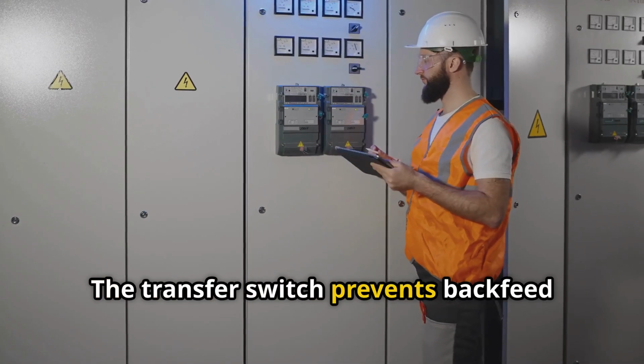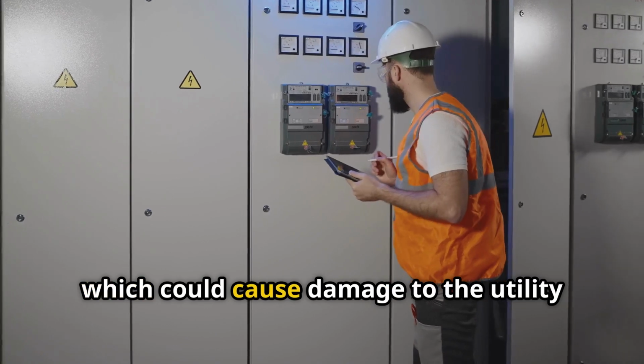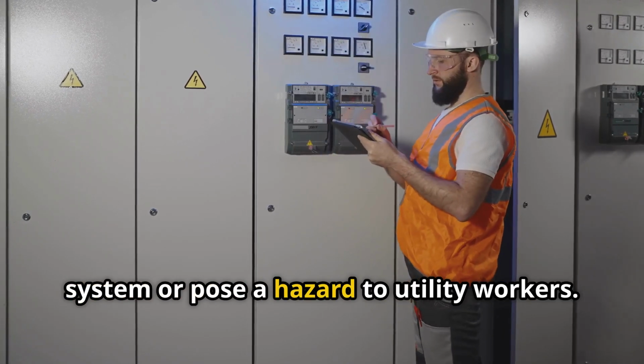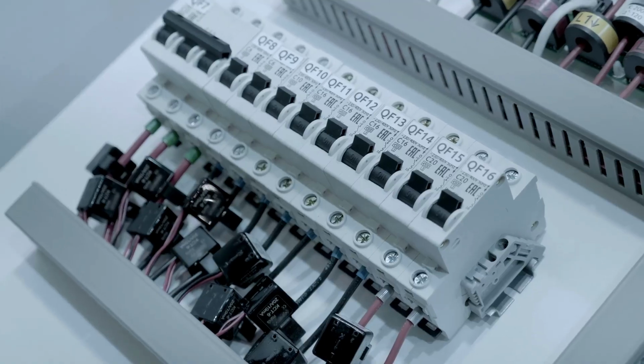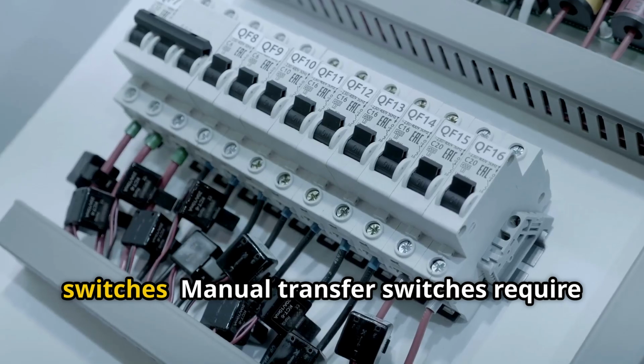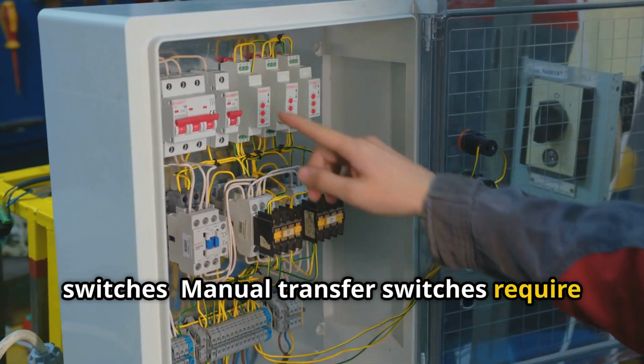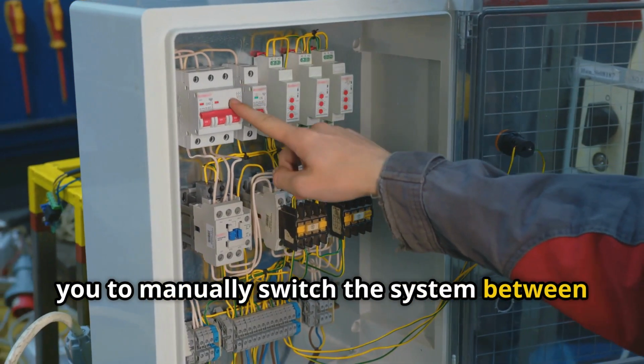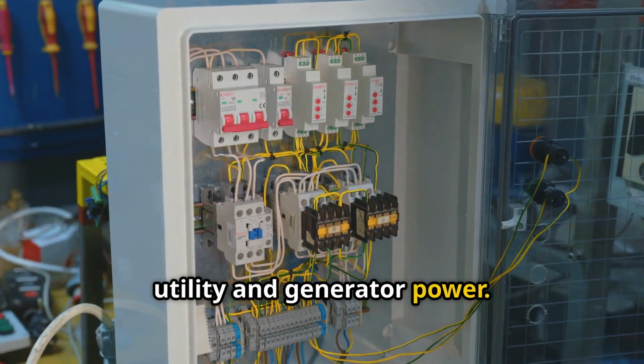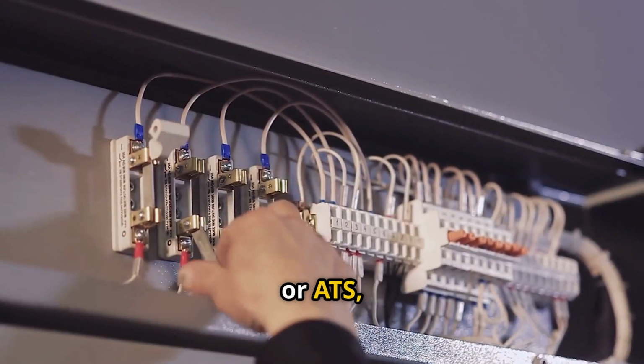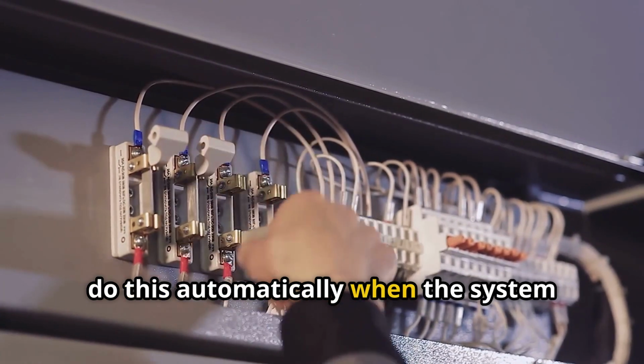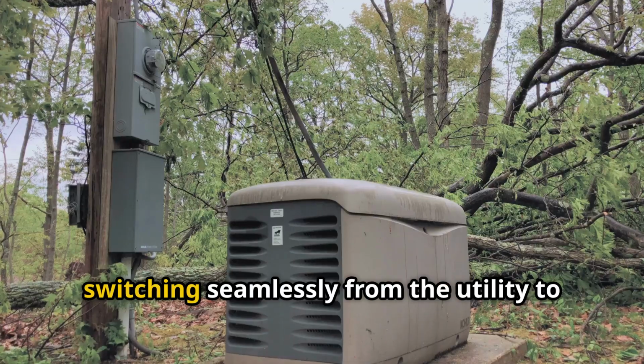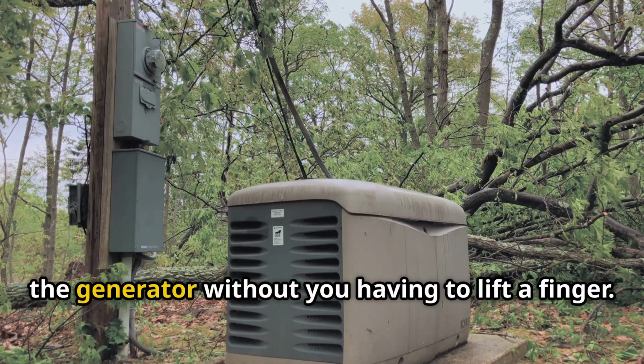The transfer switch prevents backfeed into the grid, which could cause damage to the utility system or pose a hazard to utility workers. There are two main types of transfer switches. Manual transfer switches require you to manually switch the system between utility and generator power. Automatic transfer switches, or ATS, do this automatically when the system detects a power outage, switching seamlessly from the utility to the generator without you having to lift a finger.